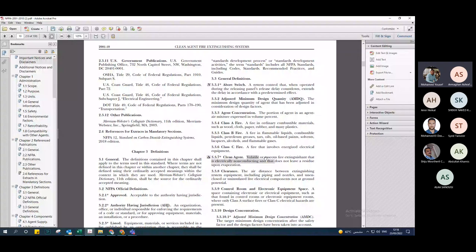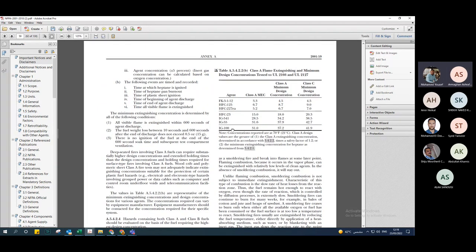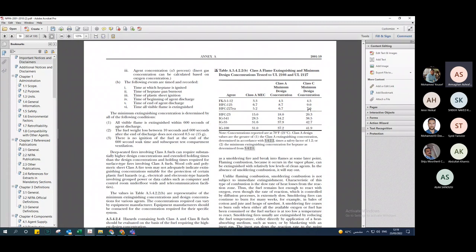For example, a switching room or communication room is a class C hazard. But a library or an area with wood, cloth, or paper is class A. Battery rooms, because they contain flammable liquids, are actually class B. Based on the hazard classification, I can directly determine the correct concentration C to use in the equation.